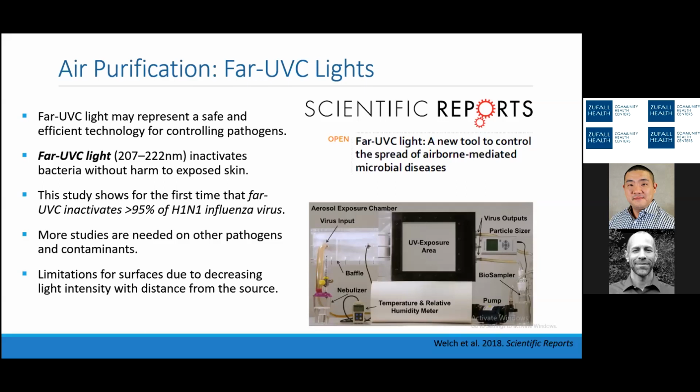There are some limitations with this technology, primarily the intensity or the effectiveness of the light decreases substantially with distance. So the intensity of light drops by the square as you increase distance. So this is one of the main limitations of this technology, but it's a very active area of research currently, and could have a lot of promise, primarily for reducing pathogens in indoor facilities, both in the air and on surfaces. However, this technology is likely not to be very effective for other types of contaminants.